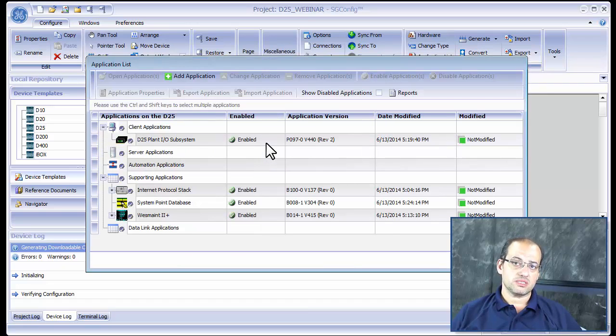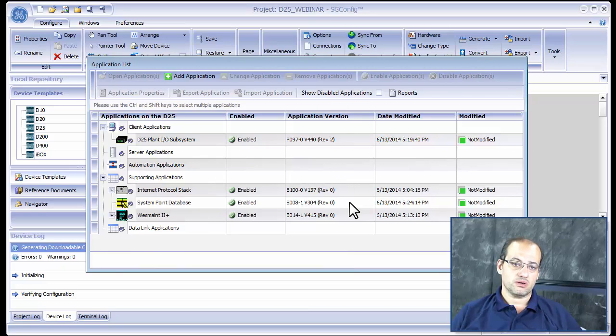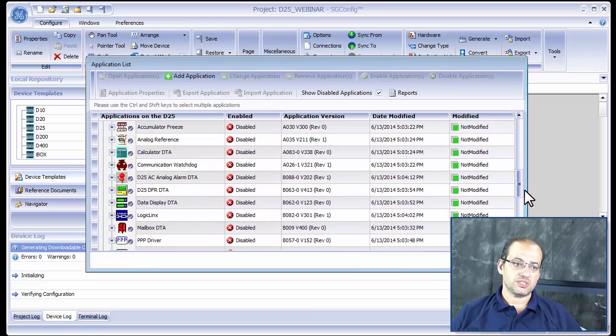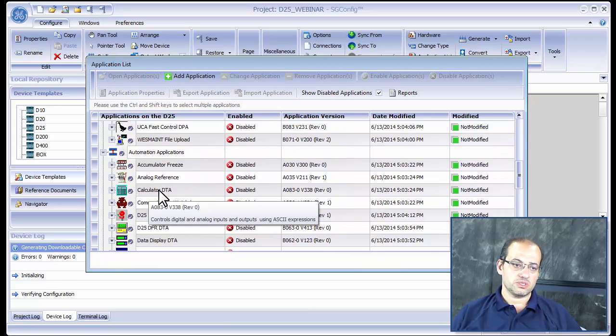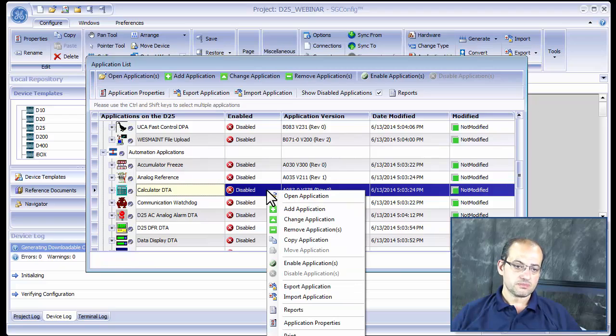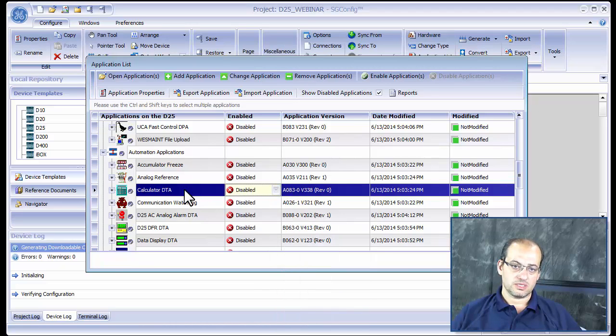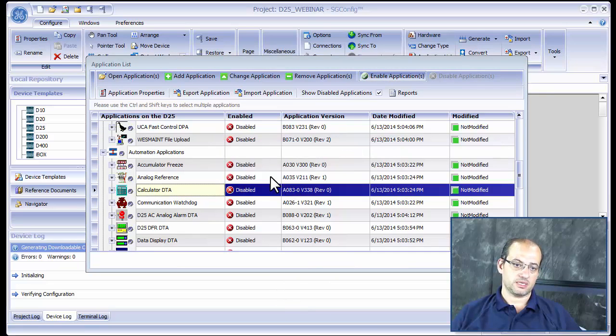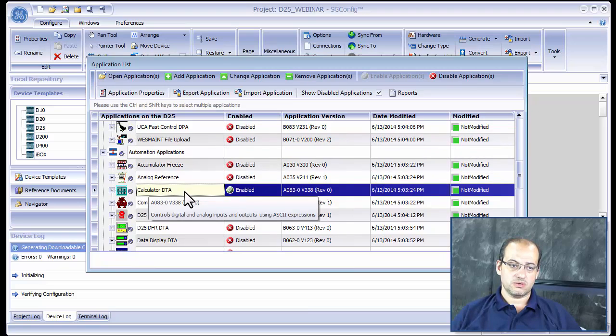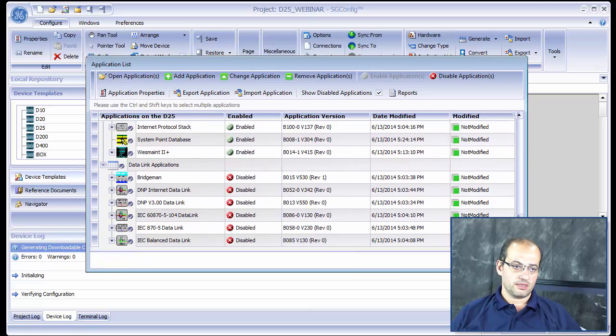The application for Calculator is A083. We have to enable that application — we don't see it on our list because we're showing only enabled applications. So we check 'Show Disabled Applications.' Application A083 is a DTA, or Data Translation Application — it changes points inside the WIN database. We right-click on it and click 'Enable Application.' Another way is to highlight the application and click 'Enable Application' that way.